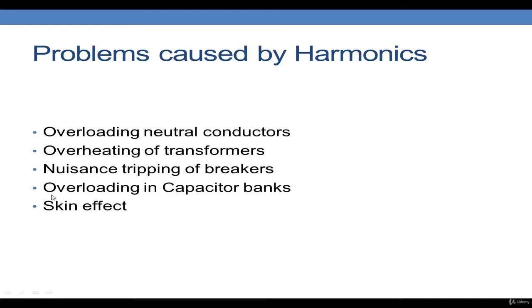Overloading of capacitor banks is another concern. Capacitor banks are usually rated to operate at power frequency. Large amounts of harmonics can cause overloading because capacitive reactance is inversely proportional to frequency. As frequency increases, capacitive reactance decreases, causing the capacitor to act as a sink for harmonic currents.